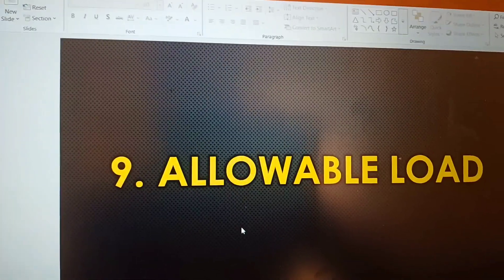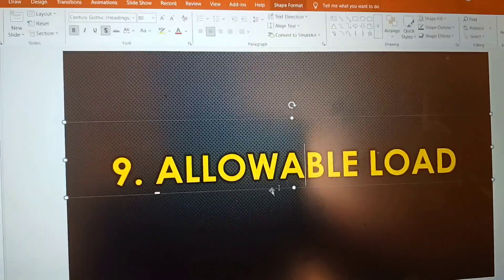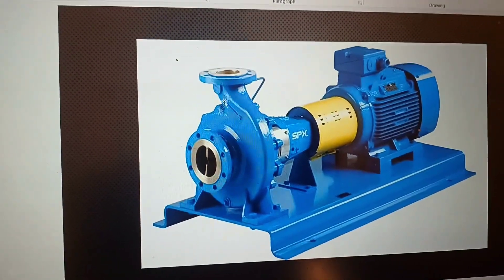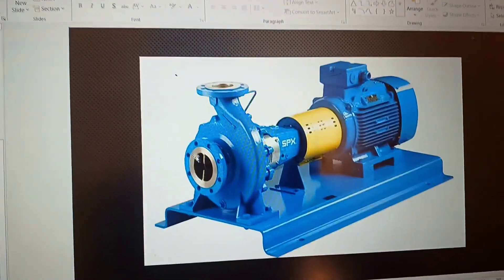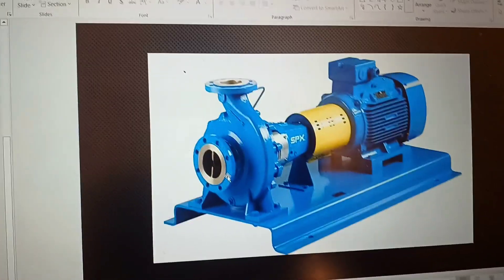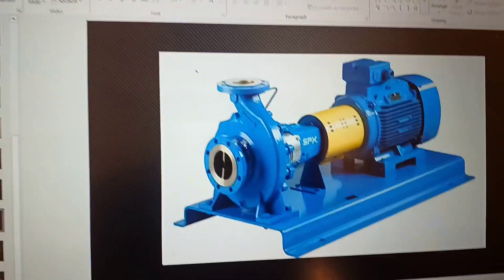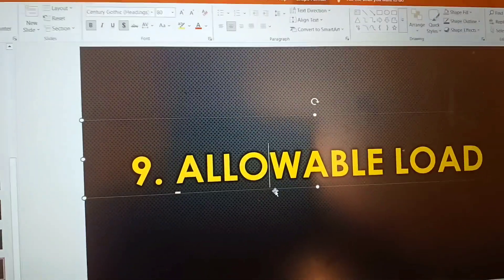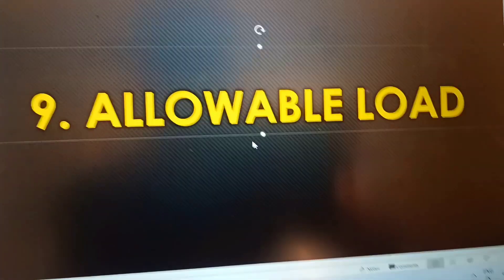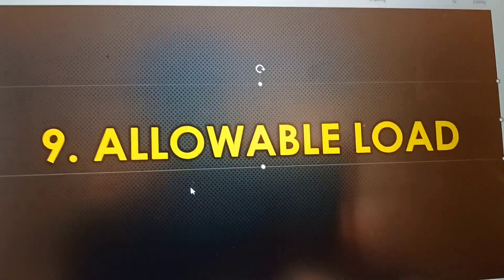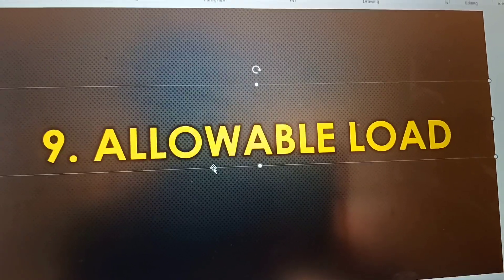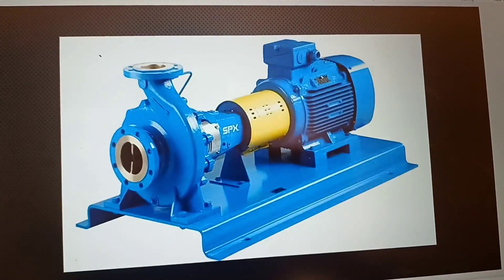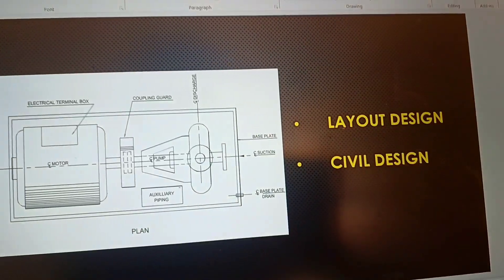The ninth point is allowable load. Allowable load is the load that the suction and discharge flanges of the pump can withstand. Once you know the allowable loads, the stress engineer can check whether these loads are sufficient to handle the connected piping. As a piping design engineer, you must ensure this input is received from the vendor — if the vendor is not ready to provide it, you must request and obtain it, then pass it to the stress engineer to confirm the nozzles are in safe conditions.